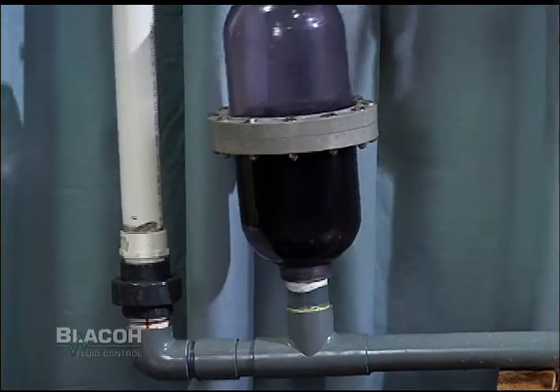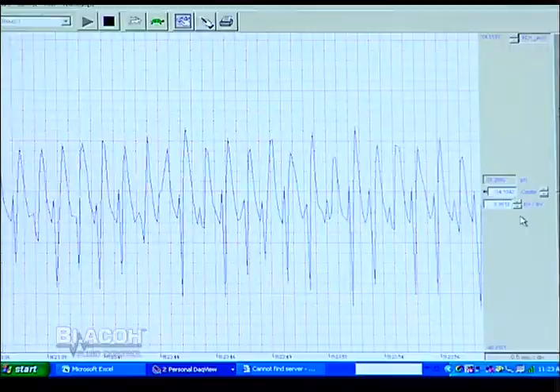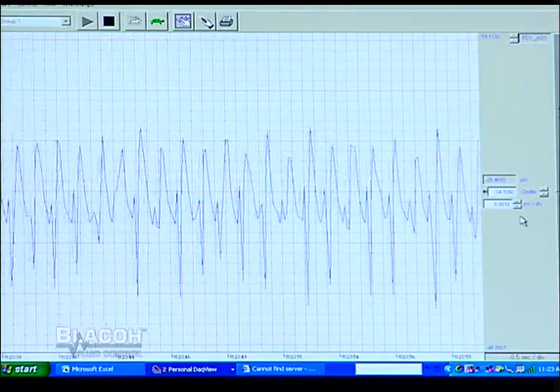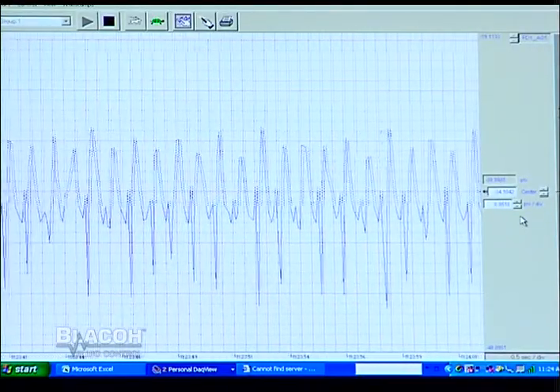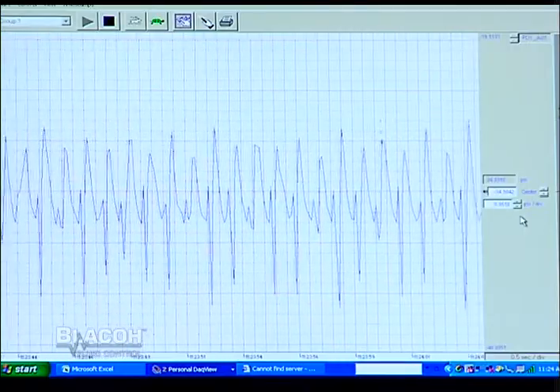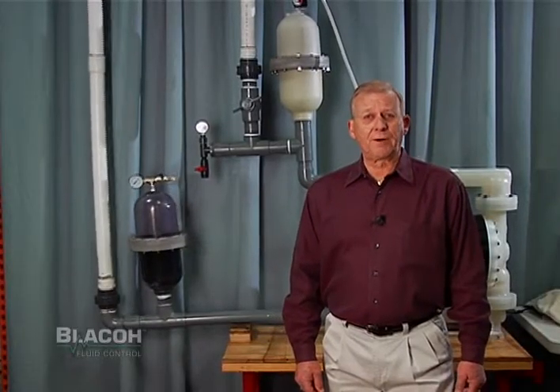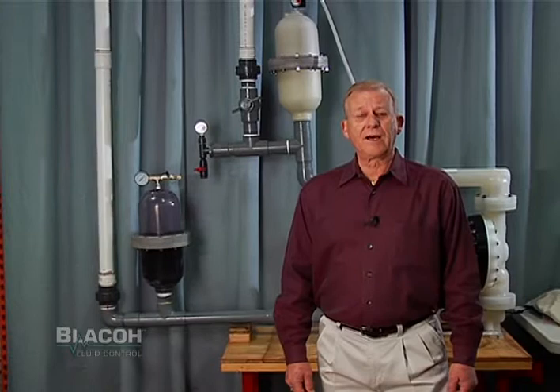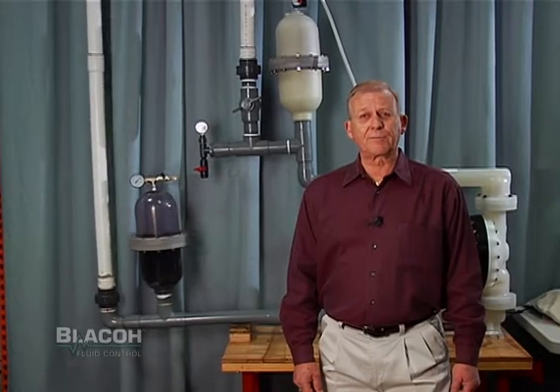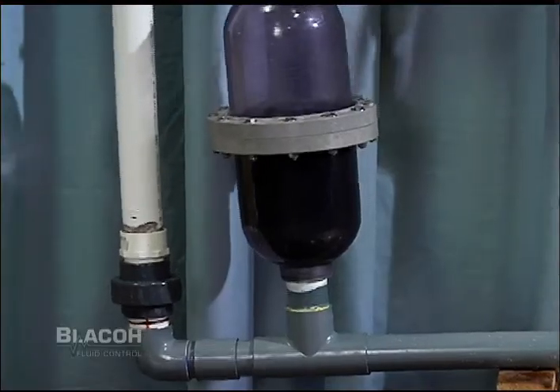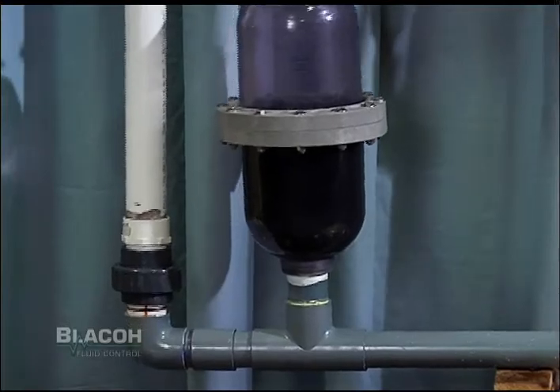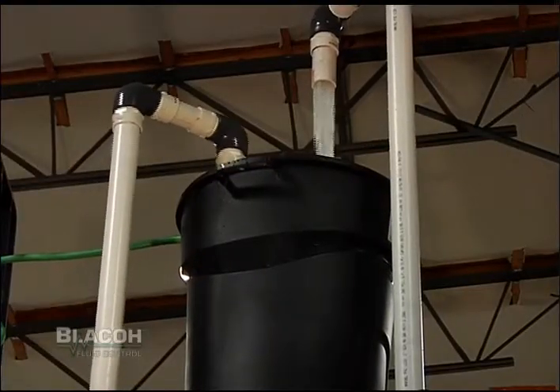The inlet side of the pump is shaking violently, and you'll notice on the transducer that with every pump stroke, the pressure spikes are reaching as high as 20 psi. Now, most air-operated diaphragm pumps tell you in their instructions not to exceed 15 psi inlet pressure with rubber diaphragms or 10 psi with Teflon diaphragms. So you can see that we can be doing damage to the diaphragms with this kind of pressure spike.